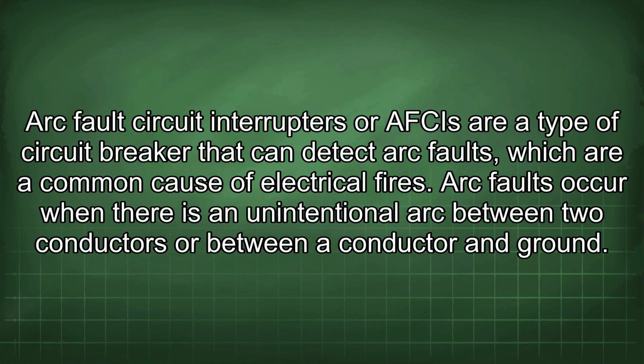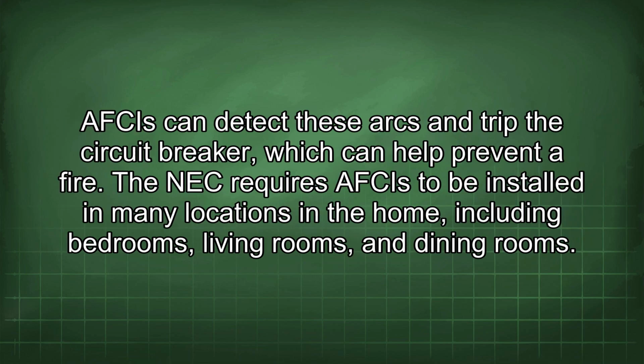Arc fault circuit interrupters, or AFCIs, are a type of circuit breaker that can detect arc faults, which are a common cause of electrical fires. Arc faults occur when there is an unintentional arc between two conductors or between a conductor and ground. AFCIs can detect these arcs and trip the circuit breaker, which can help prevent a fire. The NEC requires AFCIs to be installed in many locations in the home, including bedrooms, living rooms, and dining rooms.